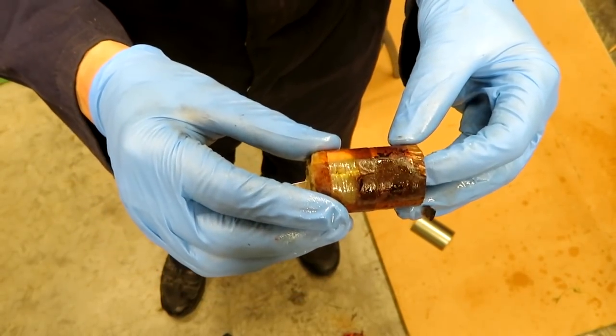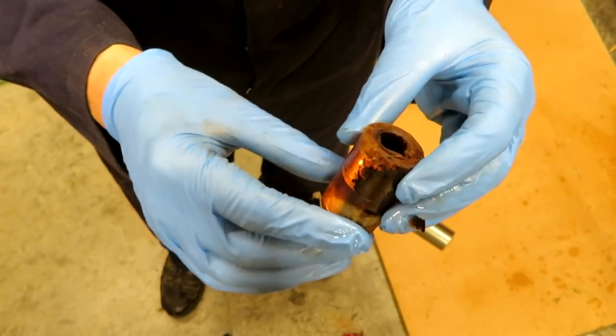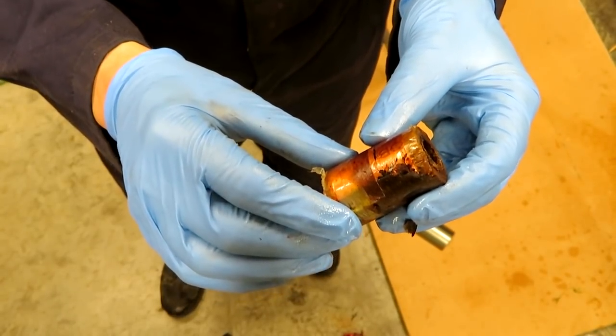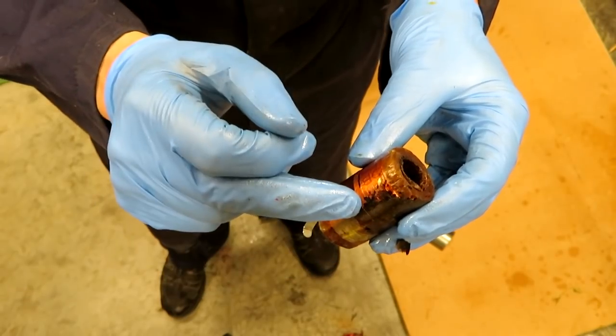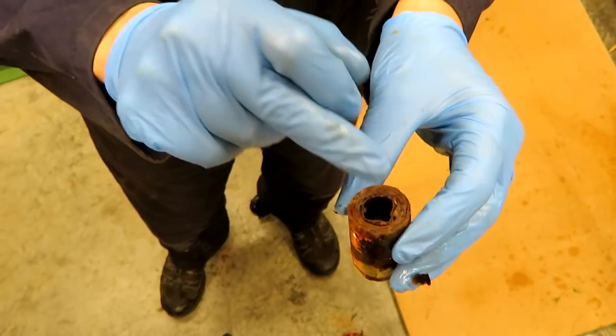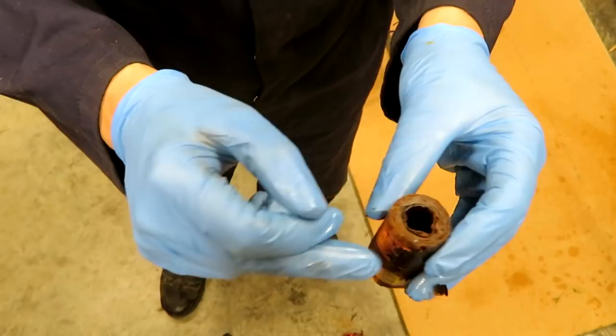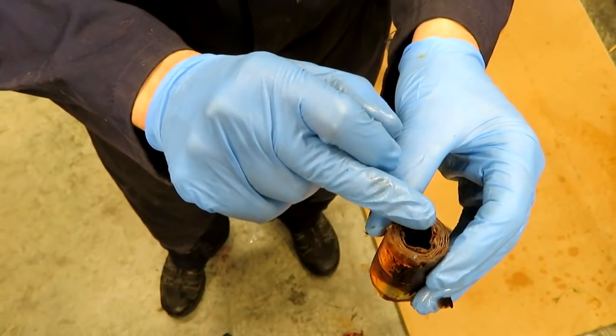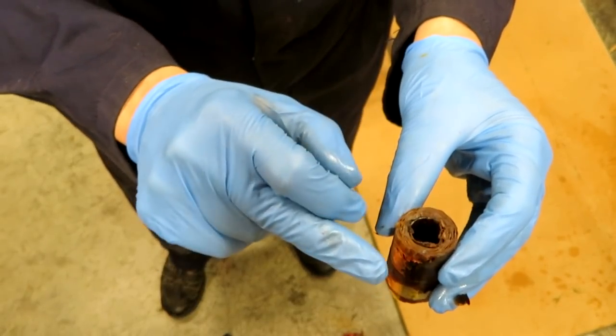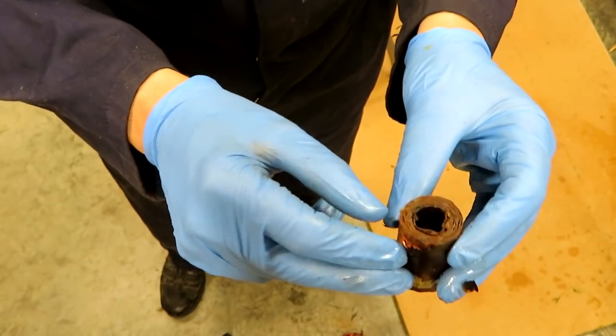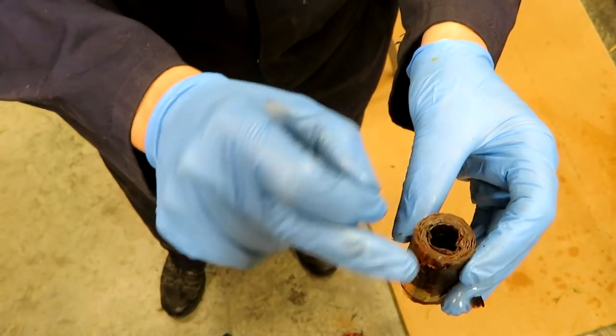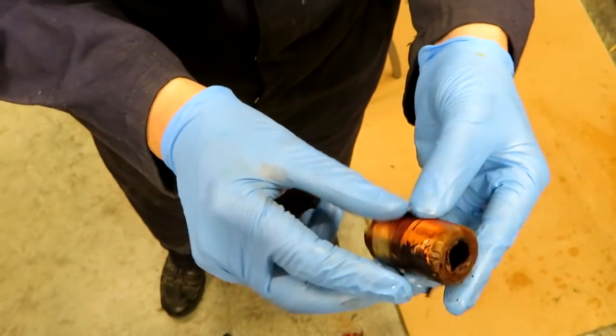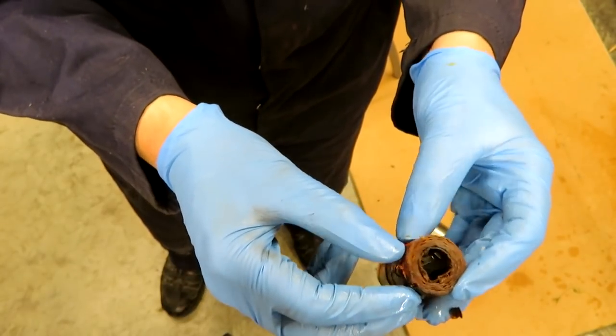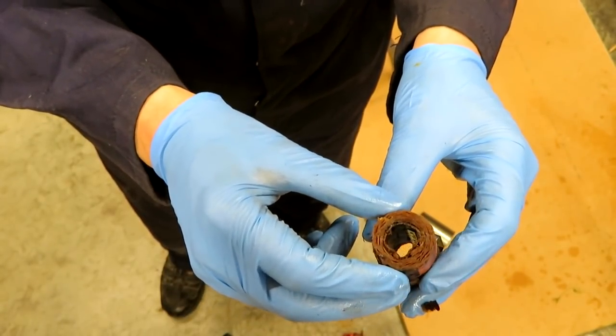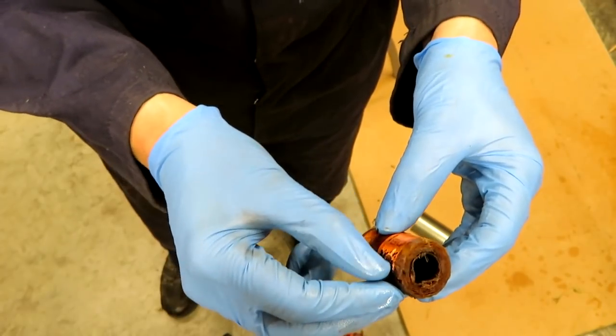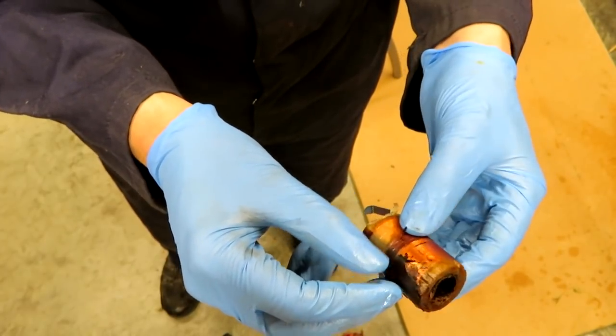The way you wind these high voltage transformers, what you've got to be very careful of is you can get a high voltage flashover from the high voltage side of the coil to the inside — let's call it from the inside of the coil to the outside. So you'll have a low voltage on one side and the voltage gets higher as you move out from the centre. But what can happen is you get a flashover between one side of the transformer, from the high voltage to the low voltage side, and when you get that flashover it can damage the transformer and cause all kinds of nasty things to happen, burning the insulation.